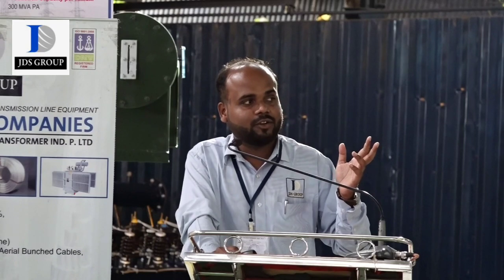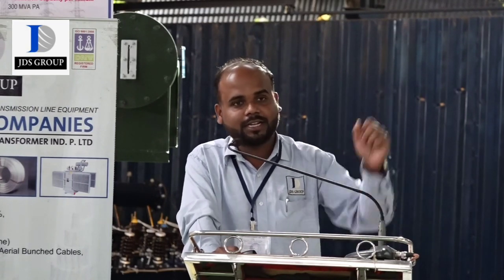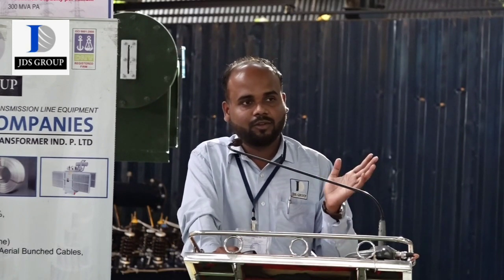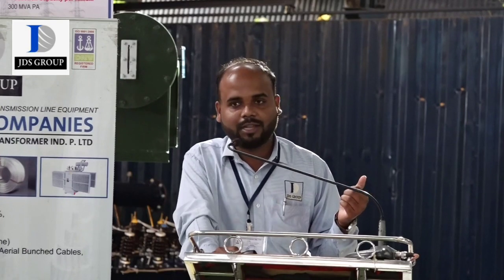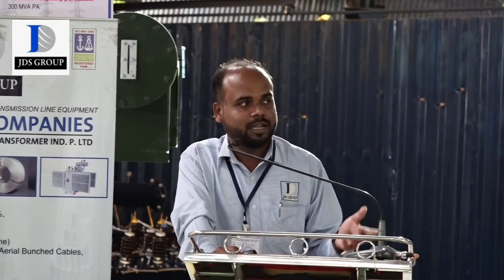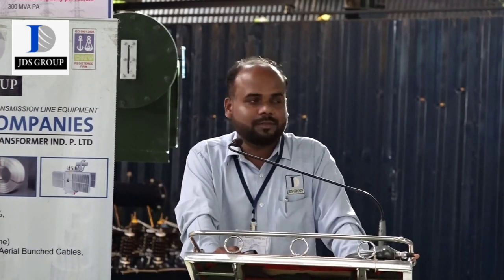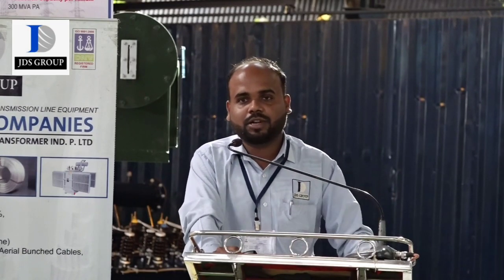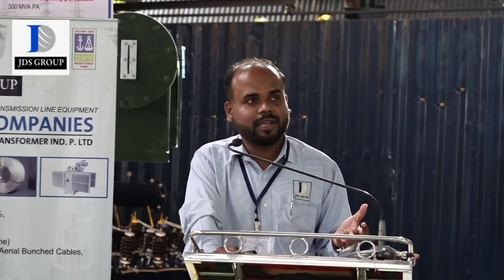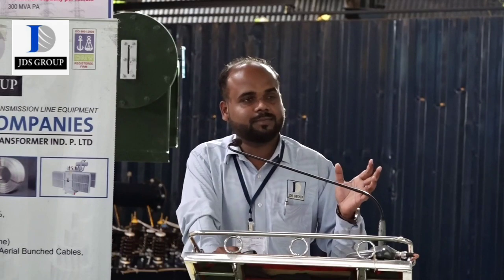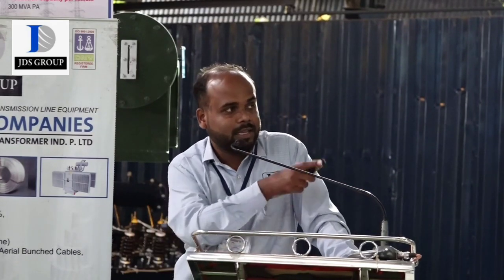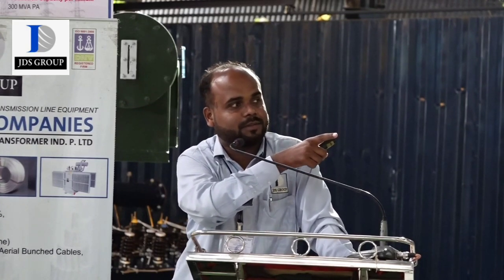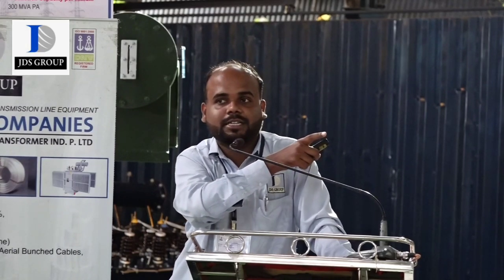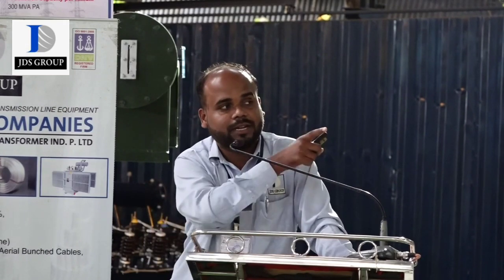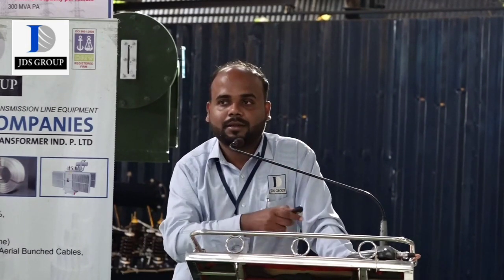After that, the magnetic oil level gauge. In some conditions the transformer oil level goes down and we are not able to know. So the magnetic oil level gauge tells us that our transformer oil has gone below the minimum level. So we will be aware that the transformer oil has come to the minimum level, and we can do the necessary things: we can put new oil into the conservator, and additional earthing is also provided to the transformer. Suppose the transformer is working under load for many hours, some gases would be released, and the explosion vent and pressure release device will also be provided. This is the image of the WTI and OTI that will be used in our power transformer. And the Buchholz relay: if some internal fault occurs in the transformer, it would not burn the transformer. Automatically the Buchholz relay will signal the control panel and the whole system will be stopped.